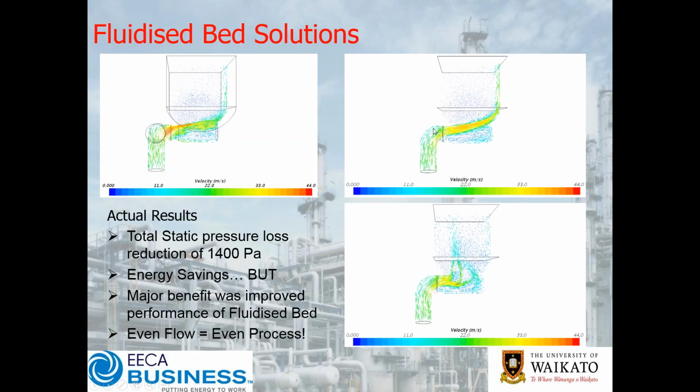And so you can fix this elbow, which has reduced the airflow a little bit, but then ultimately what we ended up doing is, by some careful treatment of the flow, we can spread that across that bed. Now, of course, what we've deliberately done here is we've given no bias to any spreading from pressure drop across a bed plate in there, and we've done that very deliberately, and I'll explain a little bit more about that in a minute. But what were the results and outcome of this?